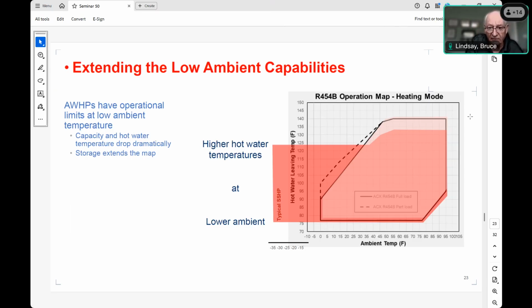What's really interesting for us is, if we go back, I'm using my water in the tanks as a source of heat. So if I look at 32 degrees, go all the way up and see where it intersects that line, you can see I can produce 125 degrees of hot water. That's the key here. We're making ice in the winter to make hot water. I should mention that we have other heat pumps that are using different refrigerants. This is using R454B. We have other ones that can actually produce up to 165-degree hot water. However, they're a lot more expensive. Next question, next slide.